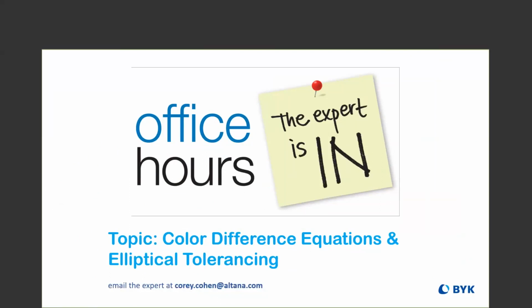A question from Jody here. What type of spectrophotometer is recommended for measuring matte finish silver? Matte finish silver. You could use either of the major geometries, 45-0 or sphere.